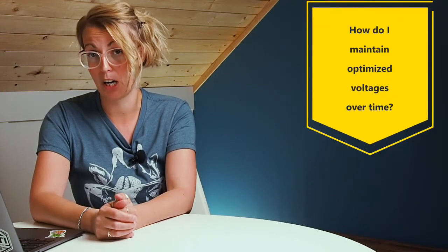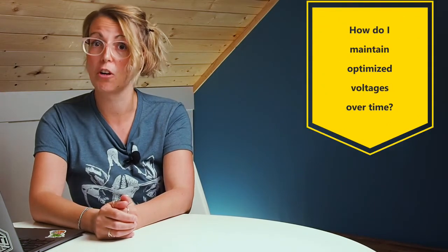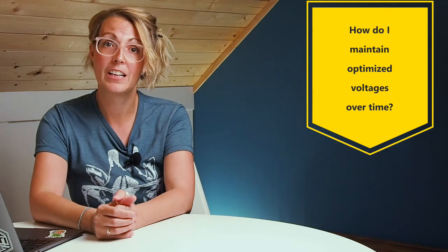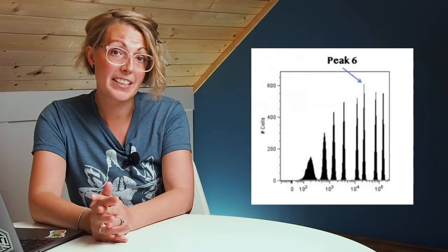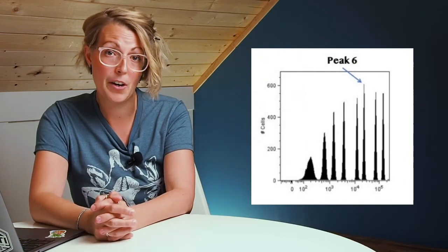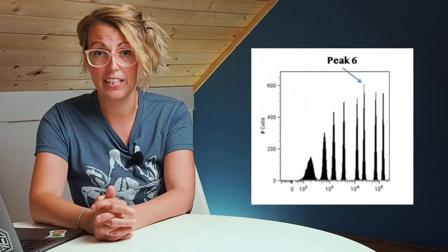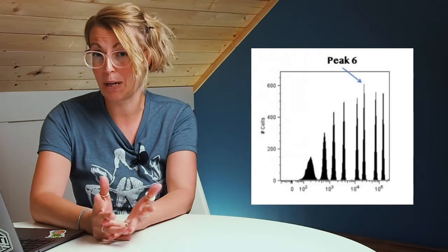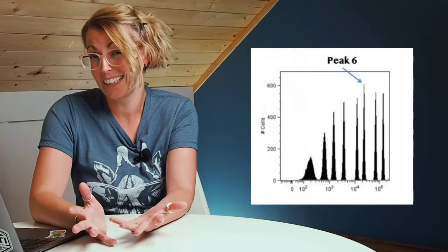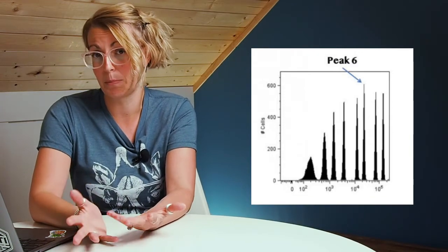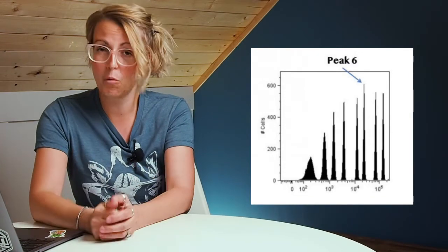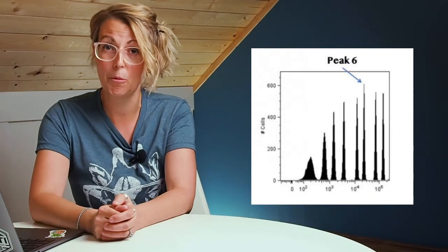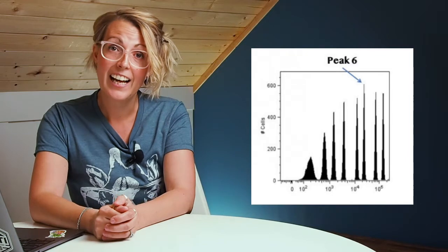After people have gone through the process of setting up their optimized voltages, I get two major questions. First, how do I maintain my optimized voltages over time? For this, I actually recommend going back to the rainbow beads or another form of calibration bead. Using these beads, you're going to set a gate around a peak population. Using the rainbow beads, I like to use peak 6, but pick your own peak.